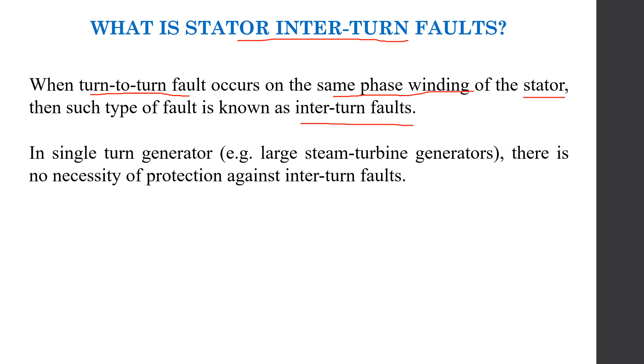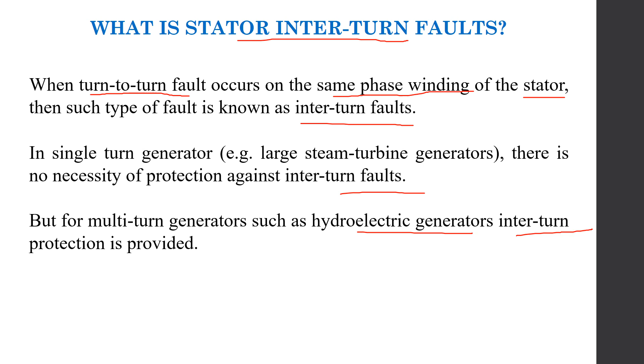In case of single turn generators, like steam turbine generators, there is no necessity of protection against inter-turn fault. But in case of multi-turn generators, such as hydro generators, there is a need of providing the protection against inter-turn fault, as these generators have double winding armatures. That is, each phase winding is divided into two halves. Therefore, it becomes necessary in case of multi-turn generators that the inter-turn fault protection must be provided.